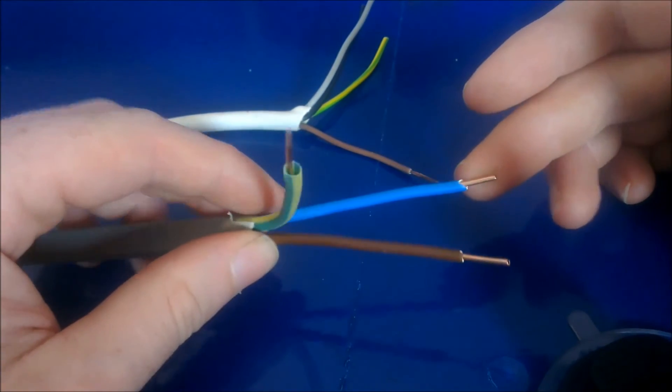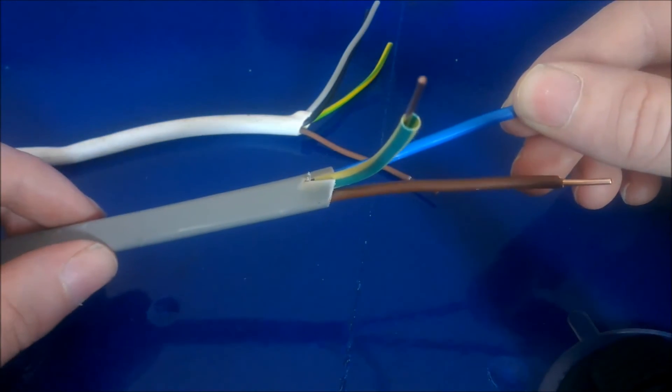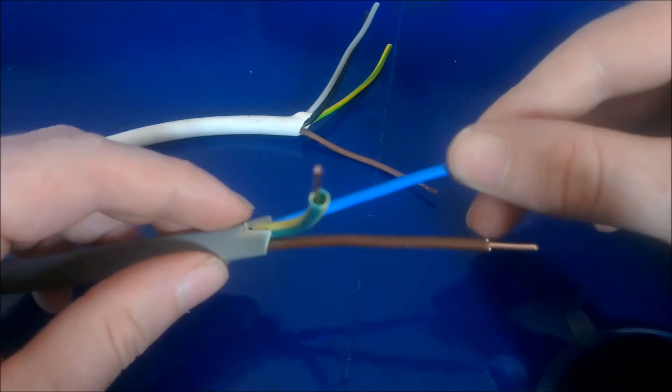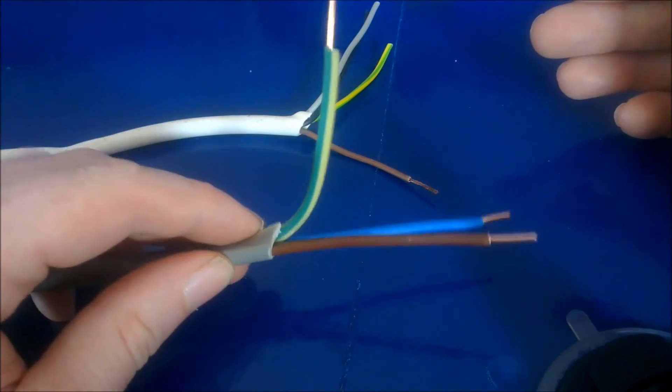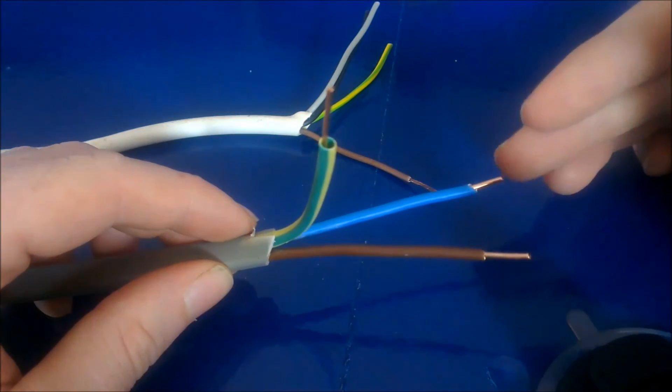But in comparison, in perfect conditions, a 2.5mm can carry up to I think it's 27 amps. So a 1.5mm cable can only carry up to 16 amps, so you can see the difference there.